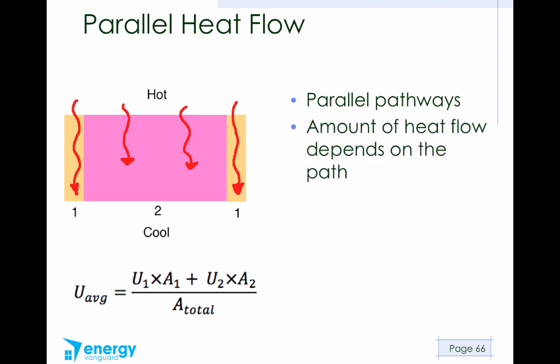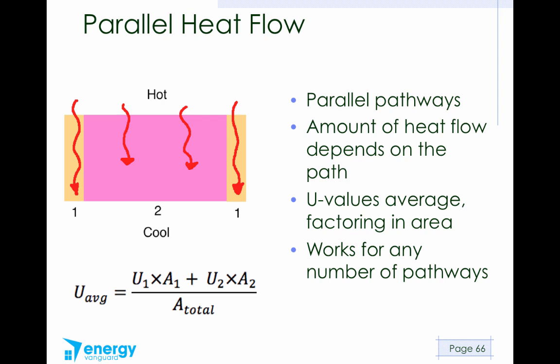The amount of heat that travels through the assembly depends on which path it takes. The way we handle this is that we average the U values using this formula. In this case, we have only two types of pathways, one and two, so we're going to multiply the U value for pathway one times its area, and then add it to the multiplication of U2 and A2. We do all that math on the top, then we divide by the total amount of area, and that will give us the average U value. This works for any number of pathways. I've shown it for only two pathways here, but if we had 50 pathways, it would still work. We would just have to add more terms into our equation.